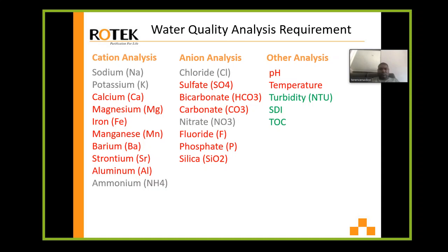If you see reddish water on the concentrate flow meter, that's iron. Okay, manganese is black. So if you see some black particles or foulants on the membrane, then it may be caused by manganese.